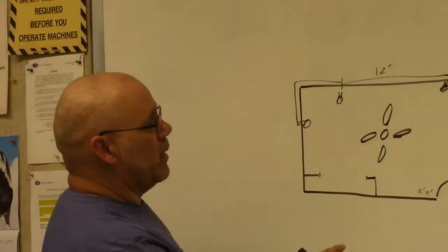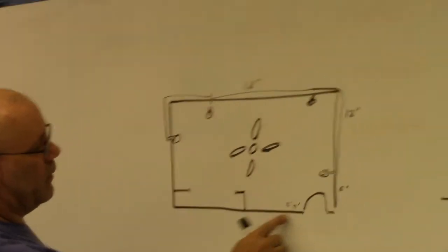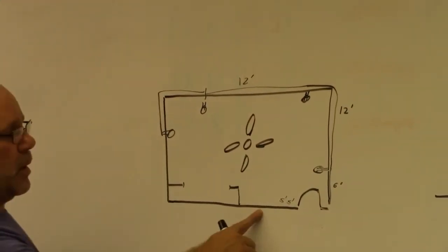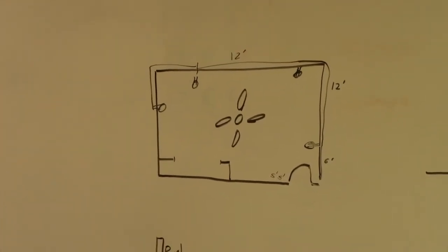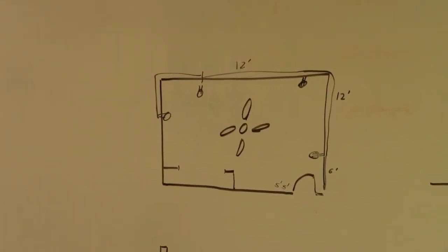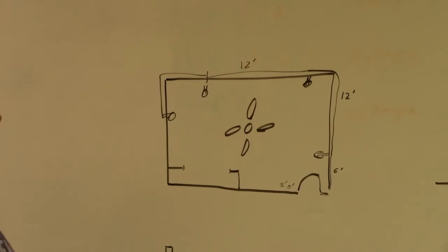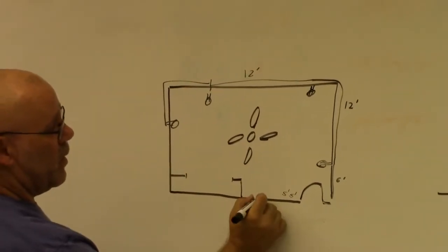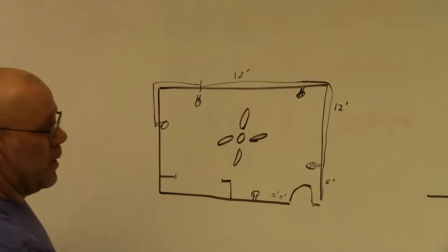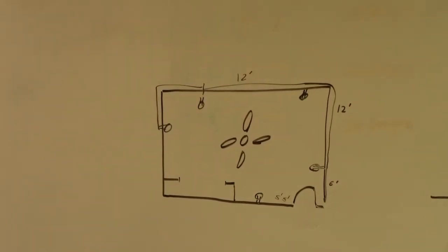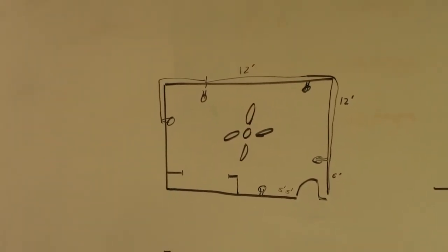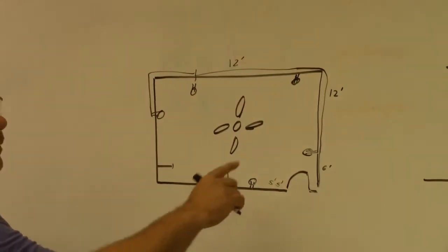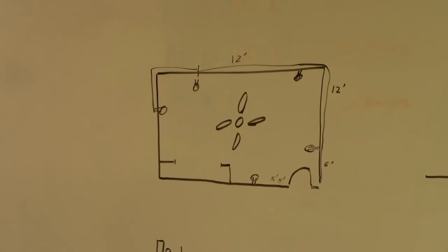Now that leaves this wall right here. If this wall is more than two feet, it has to have an outlet. So this wall is going to need an outlet. So now I have all my outlets identified, where approximately I'm going to put them.